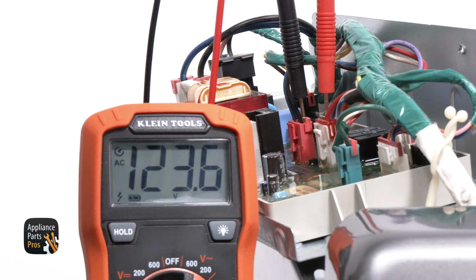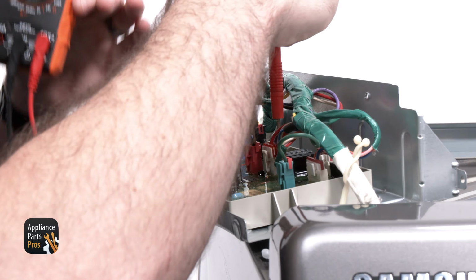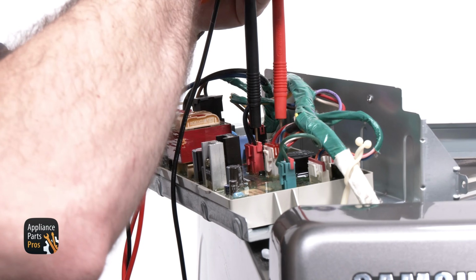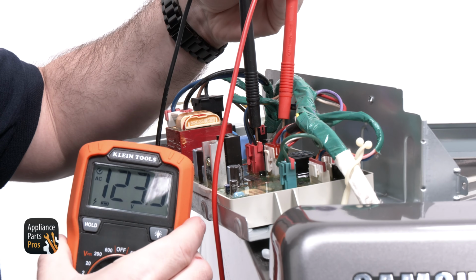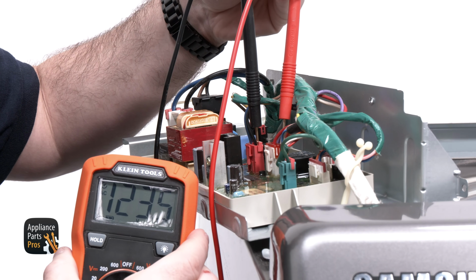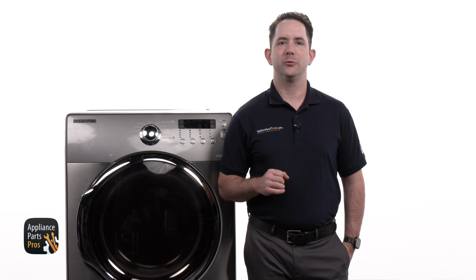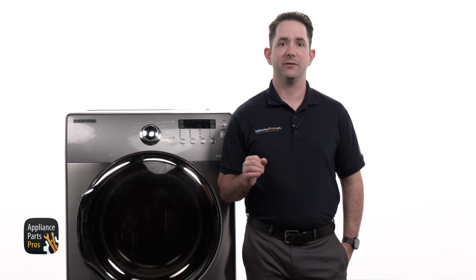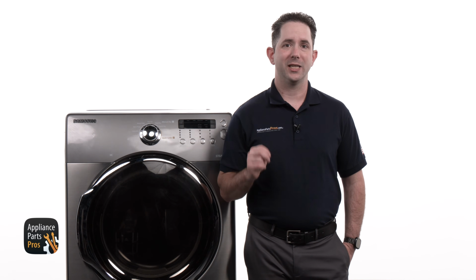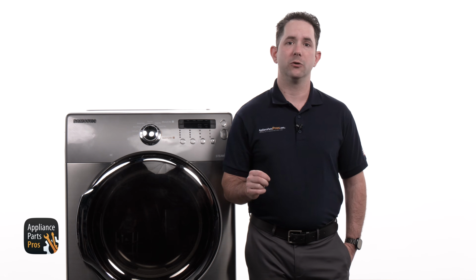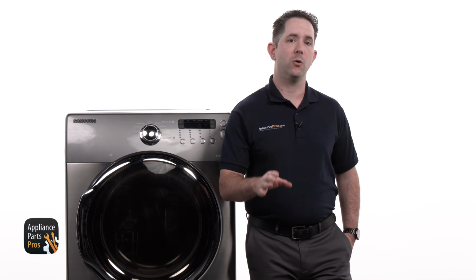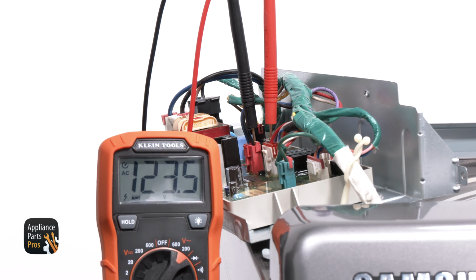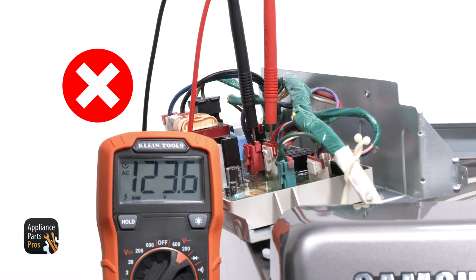If voltage is present, like we see on this dryer here, then we can move the red probe to the red wire, and we should get the same reading. If voltage isn't present at the red wire, then we'll wait 2 more minutes. A steam dryer temporarily sends voltage to the valve solenoids every 2 minutes, and it's possible that we had missed the voltage signal because of the board timing out on the steam. If voltage is present within the next 2 minutes but steam doesn't enter the drum, then the valve has failed.